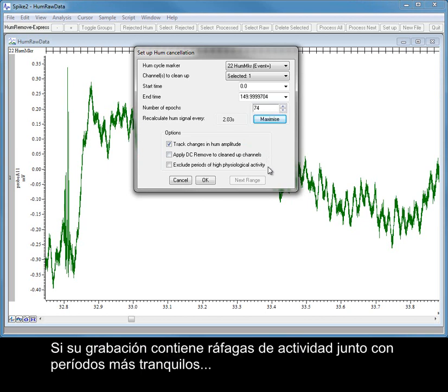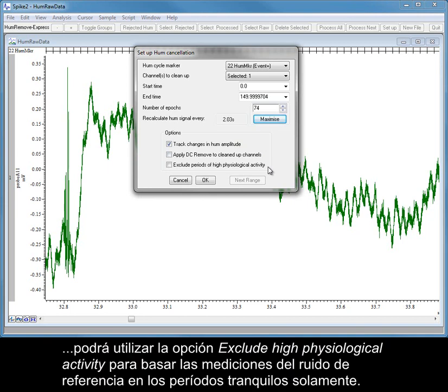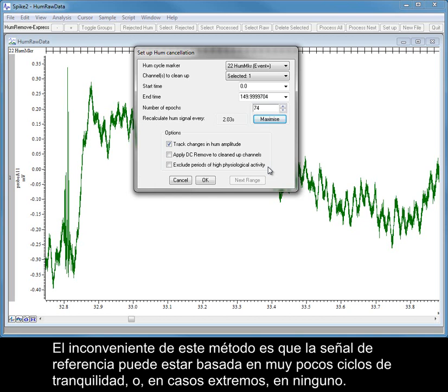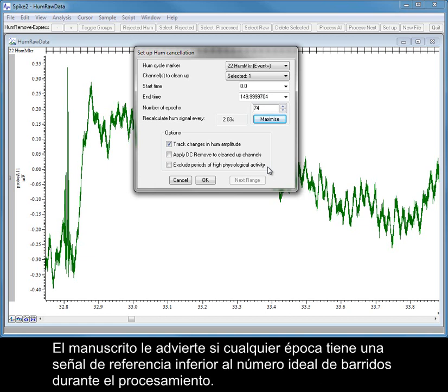If your recording contains bursts of activity alongside quieter periods, you can use the Exclude High Physiological Activity option to base the reference noise measurements on the quiet periods only. The drawback with this method is that the reference signal could be based on very few quiet cycles, or in extreme cases, none at all. The script warns you if any Epochs have a reference signal lower than the ideal number of sweeps during processing.